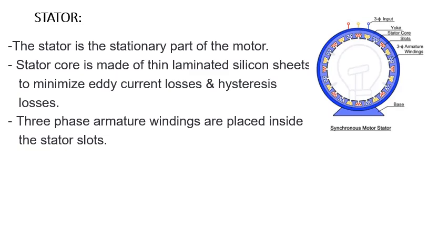Another important thing is that we laminate the stator core. We provide laminations to reduce the eddy current losses. If we use silicon steel sheets, it will also reduce the hysteresis losses. These are the iron losses. So laminations are provided to reduce eddy current losses, and silicon steel reduces the hysteresis losses. These are the major things associated with the stator.